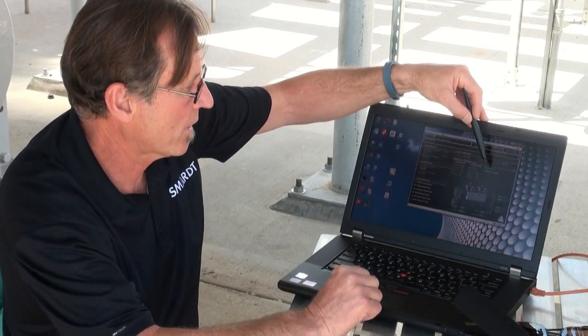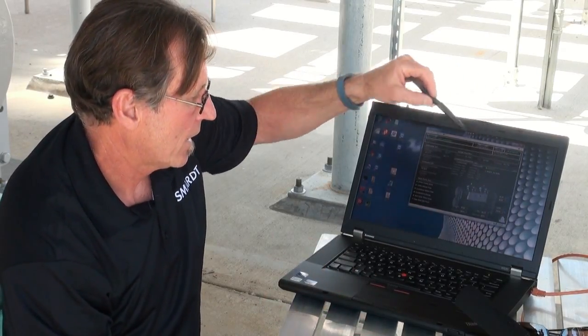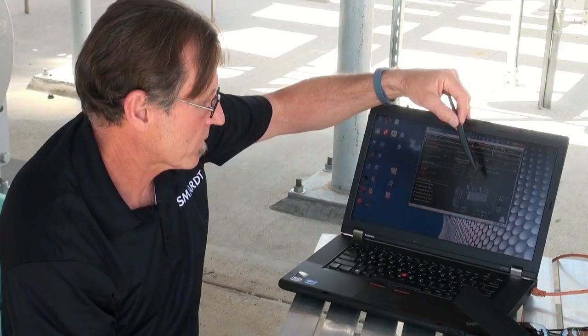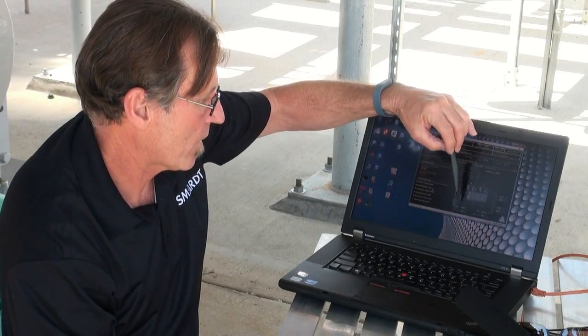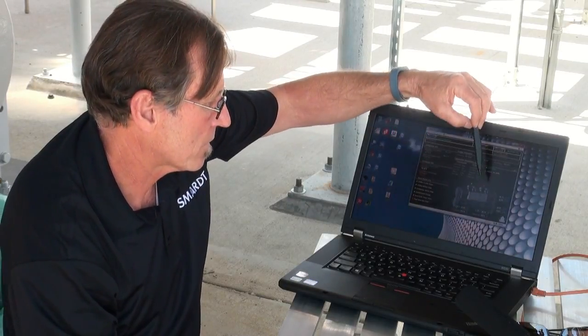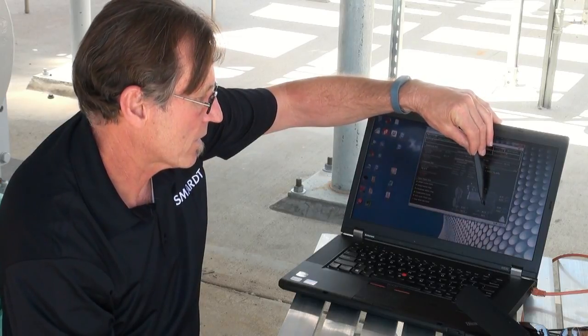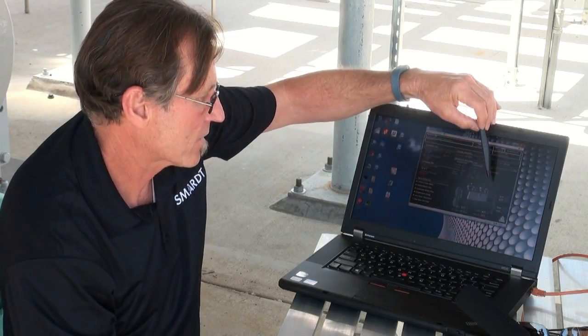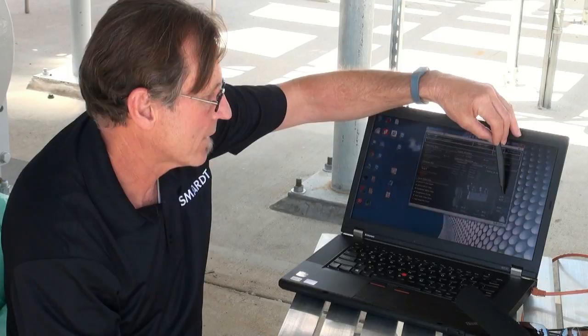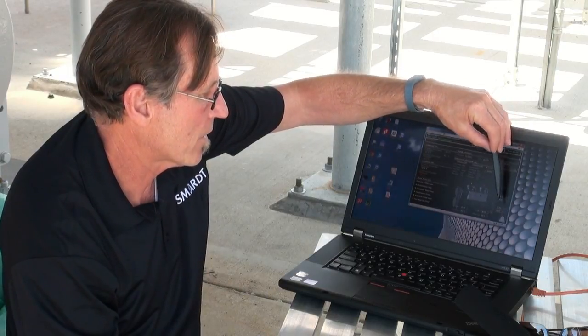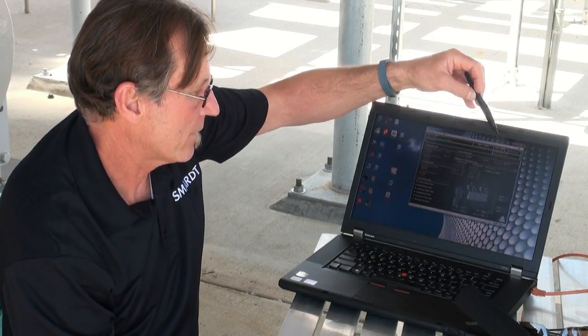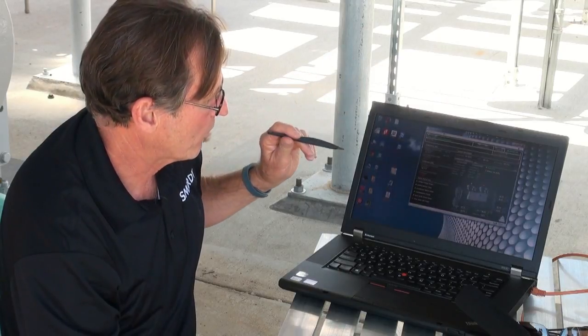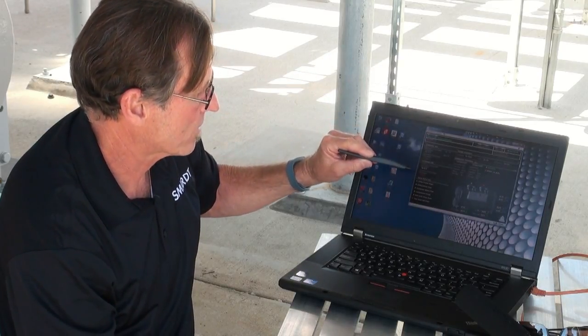But as long as it is ready to run, then you're good to go. You've got some chiller information. You've got saturated evaporating temperatures, EXV position, condensing temperatures, and hot gas position. Again, you've got chill water in and out, condenser water in and out. A lot of information.